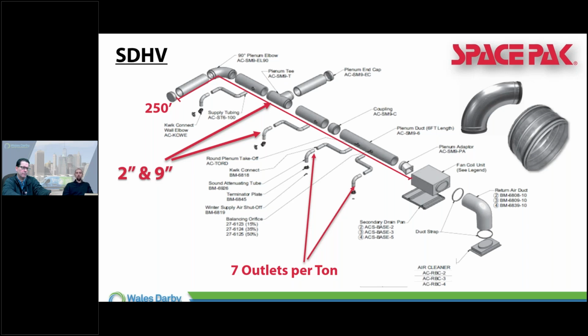Once we start getting into the zones though, we got to look at those outlets per ton, they start to bump up a little bit. We got to have a minimum. If you are utilizing some of the inverter technology today with heat pumps, some of the condensers out there today, that definitely makes it interesting, because traditionally with an AC-only system, we really can't change the capacity coming out of that condenser. So we always got to have the proper airflow. There are no bypasses like a traditional system, but we do have to have a minimum amount of airflow. So we got to pay special attention to how many outlets per ton we have there.